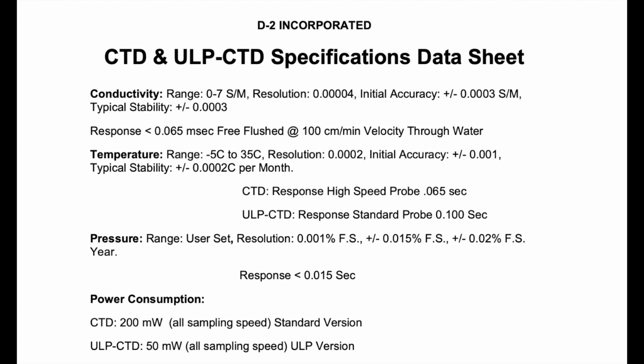Our CTD line comes with temperature thermistors that have a range of -5 to 35 degrees C, a resolution of 0.0002, an initial accuracy of plus or minus 0.001, and a typical stability of 0.0002 Celsius per month. This allows us once again to meet the highest performance standards. Our temperature thermistor shows a very high response speed and no spiking in the lab with a high-speed probe, 0.065 seconds. We also offer a wide variety of pressure transducers to go with the CTDs.